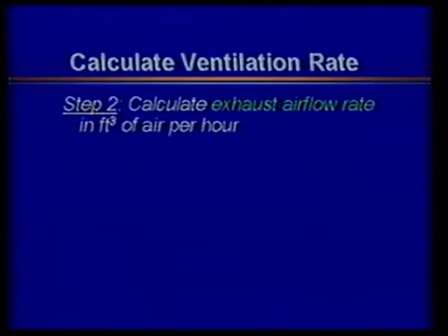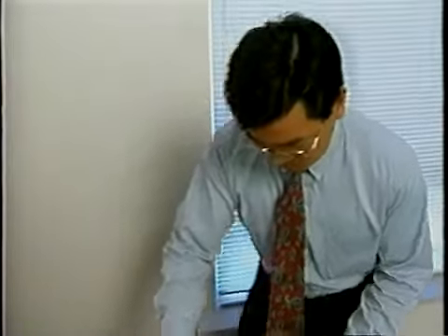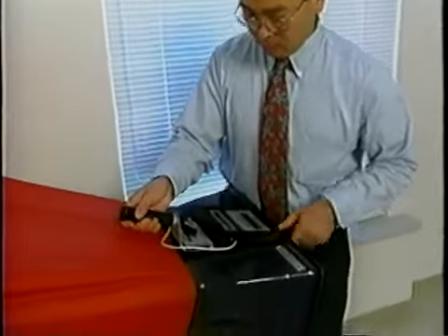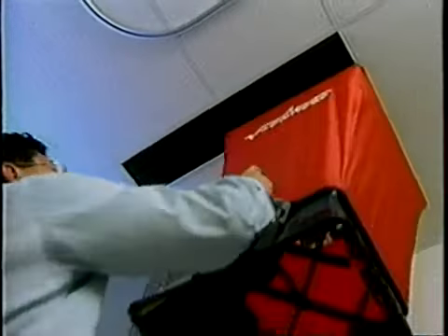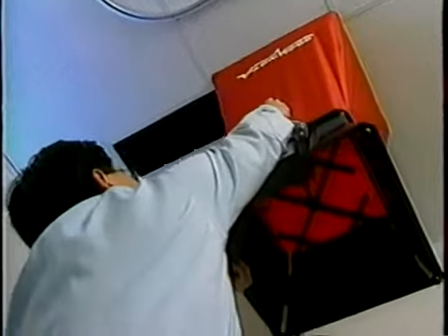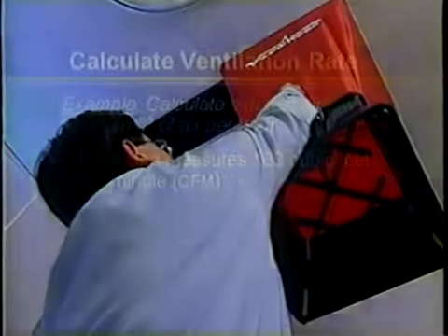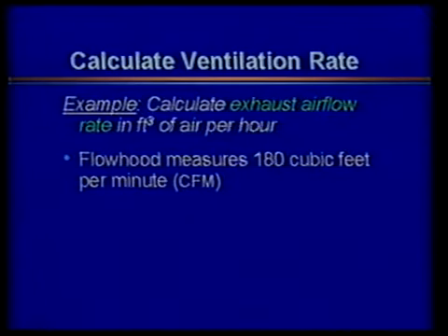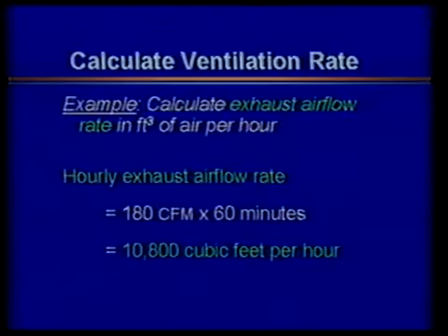Step 2: calculate the amount of air exhausted every hour. Measure the exhaust air using the flow hood. Flow hoods usually display the airflow directly in cubic feet per minute, or CFM. Multiply the cubic feet per minute by 60 minutes to determine the cubic feet of air per hour. Going back to our example, if the flow hood reads 180 CFM, multiply this by 60 and you get 10,800 cubic feet of exhaust air every hour.